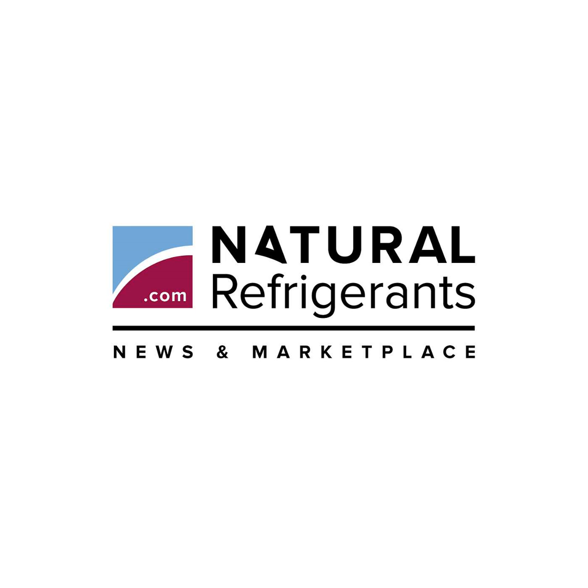CO2 pros and cons. Gibbons outlined the benefits and disadvantages of CO2 in New Zealand, including energy efficiency, refrigerant costs, and upfront system costs. CO2 systems in the country operate subcritical 90% of the year or more with a COP that can rise to between 4 and 5, he said. When it does slip transcritical, the COP drops to around 2, which is similar to synthetics in the higher ambient. In New Zealand, CO2 refrigerant is currently 96% cheaper than R404A and 92% cheaper than R449A. Initial costs remain the biggest disadvantage, with CO2 equipment running 3 to 4 times more expensive than synthetic units due to the material and plant costs required for the higher pressures.